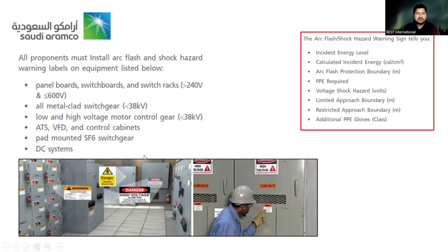Low and high voltage motor control gear, ATS, VFDs and control cabinets, even pad-mounted SF6 switchgear or DC systems. There are, of course, arc flash shock hazard warnings like incident energy level, calculated incident energy, arc flash protection boundary, PPE required, shock hazard voltage, even limited approach boundary, restricted approach boundary, additional PPE required. So you cannot allow people to just go into those areas without proper preventive and corrective measures.